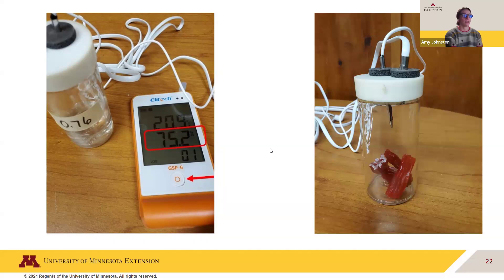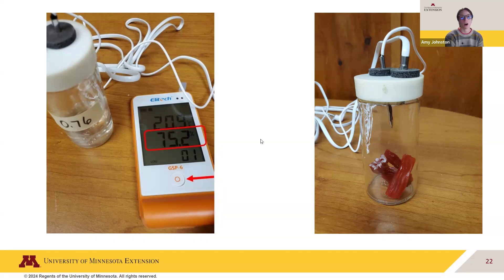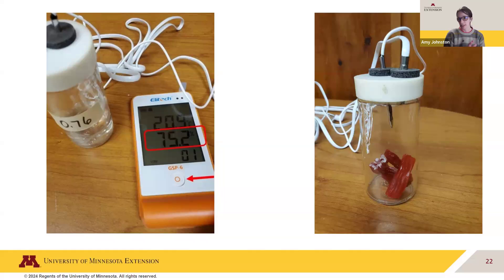Here's an image of one of the jars connected to the humidity reader device. In the bottom of the jar there are some candies. The jar is sealed with no airflow getting in, and one of the probes is in the headspace. Because the jar is sealed, over a period of time the water vapor from the food evenly distributes throughout the jar. The probe in the headspace measures that humidity once it is at equilibrium. Once the air and the food have the same humidity, we can calculate the water activity.